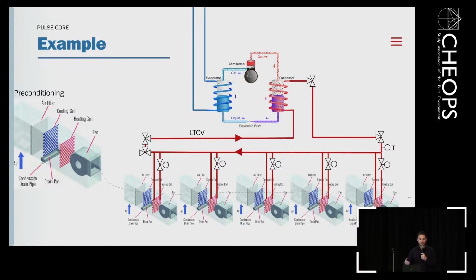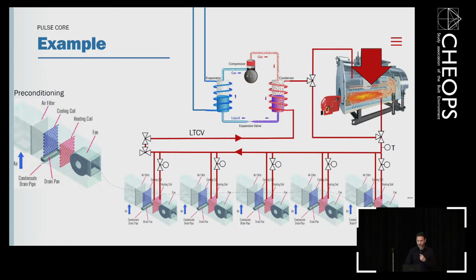We have the chiller, we use the chilled side, the cold water always. But this idea and the design process came that we could reuse the condenser side as well, so we could use the heat produced by the chiller for some final conditioning of the air handling units. Then it was thought, well, maybe this is not enough all the time.